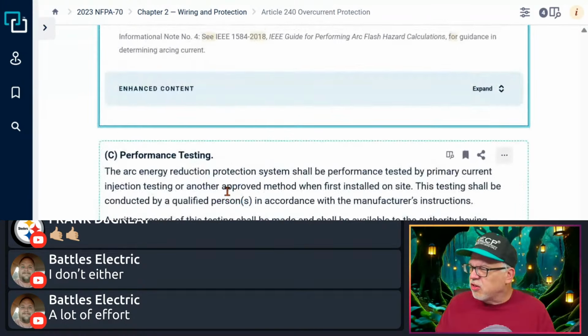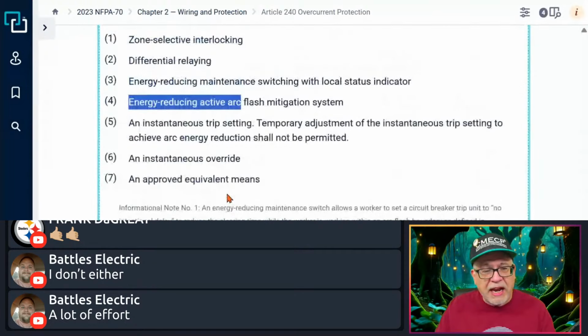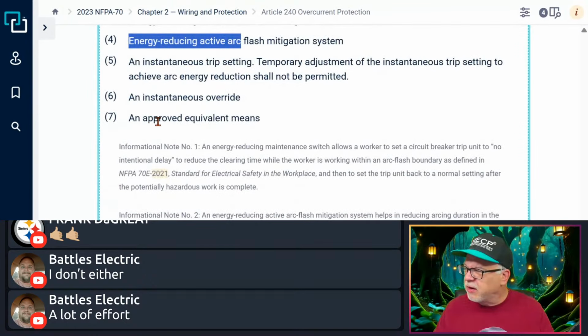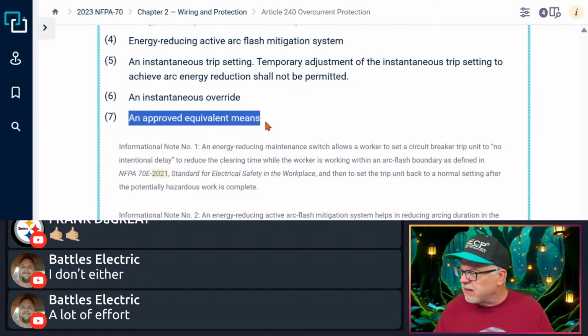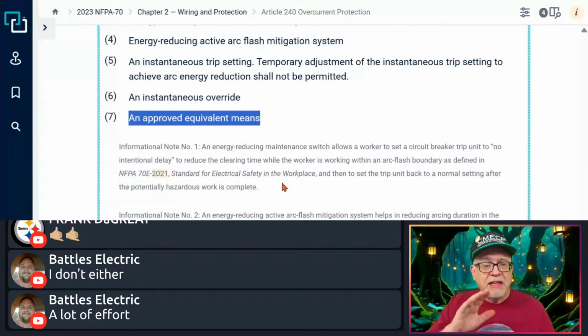But one of the things that you can also do here is, if you have a way to use current limiting, anything that can reduce the amount of energy may be acceptable to the AHJ as a method to reduce it. Just make sure you document it and that the manufacturers give you the equipment documentation to show that it is current limiting and all this kind of stuff. You want to have it as documentation. And that could also be considered an approved equivalent means, that type of thing. So again, work with your manufacturers.